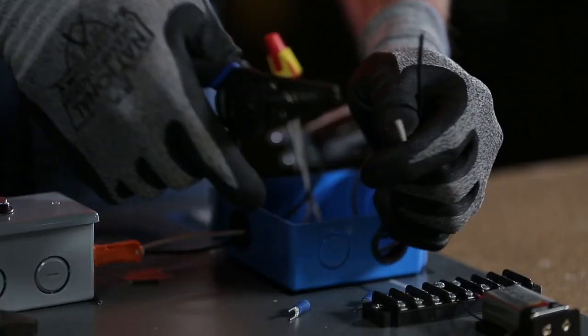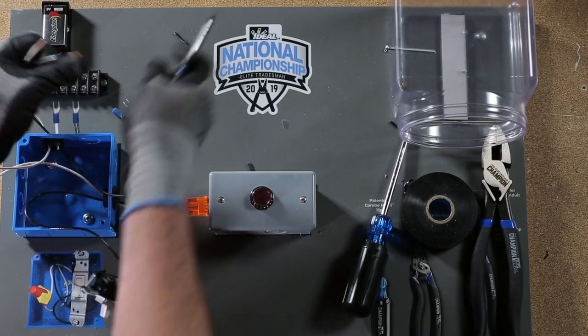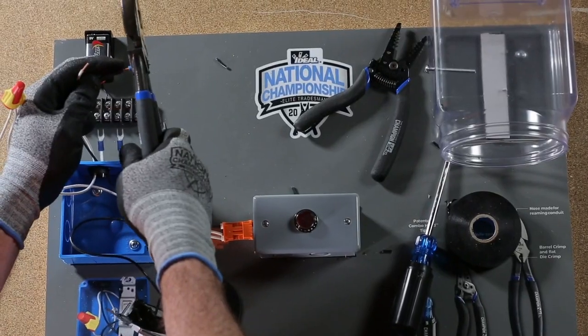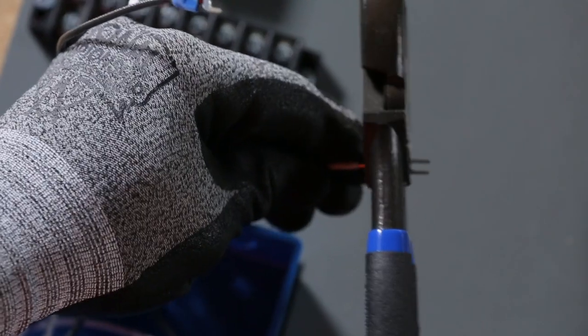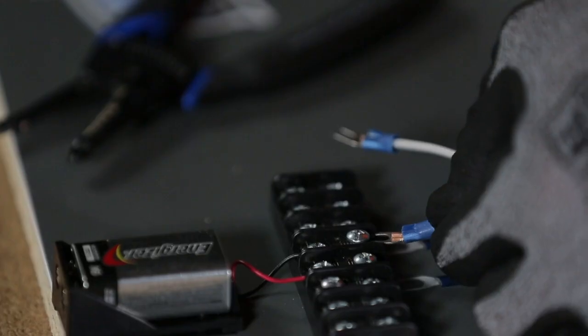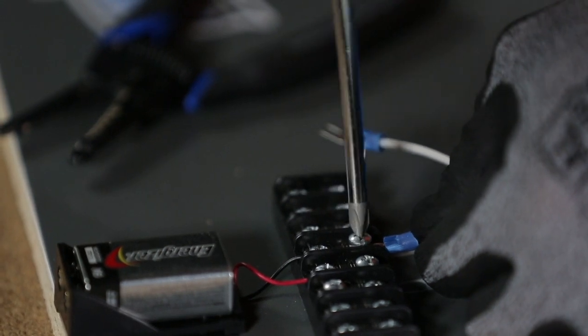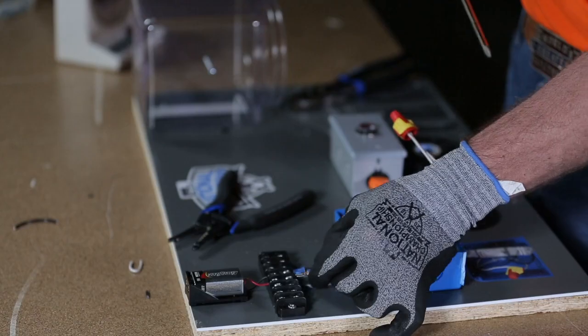Strip both ends of the wire closest to the terminal strip with the T-Stripper. Using the crimping die in your Linesman pliers, crimp the spade terminals on both conductors and connect to the terminal strip, paying attention to the polarity of your wires.